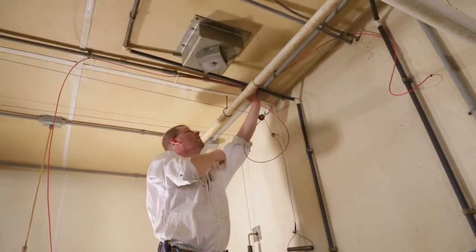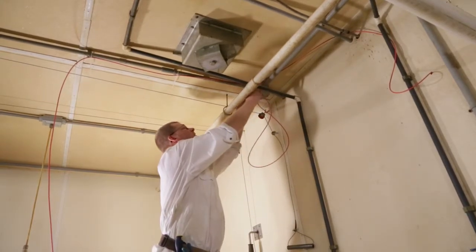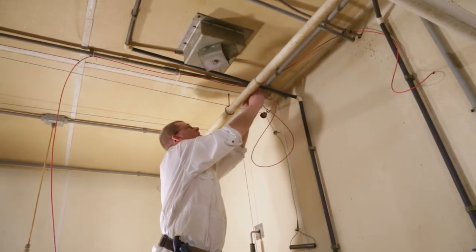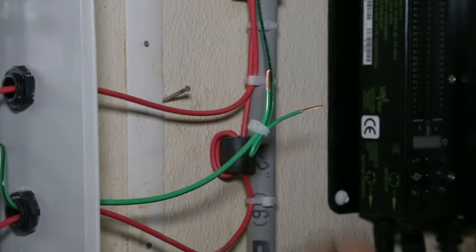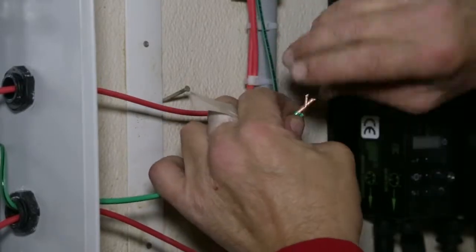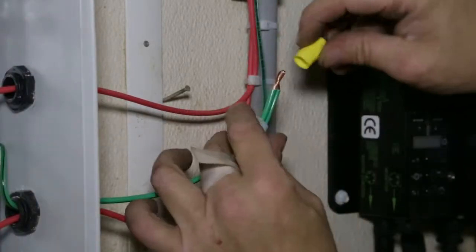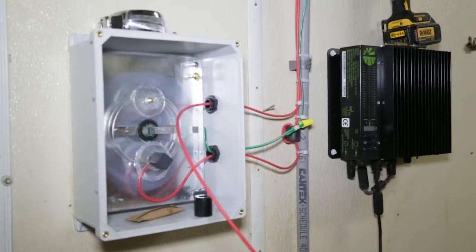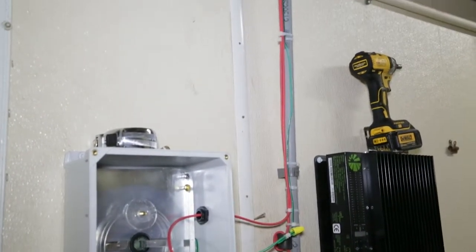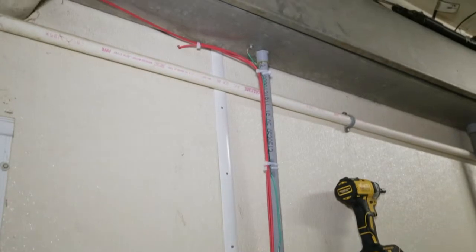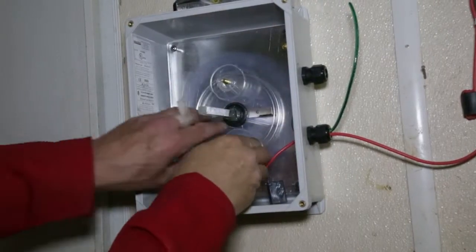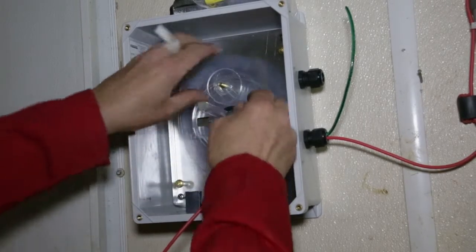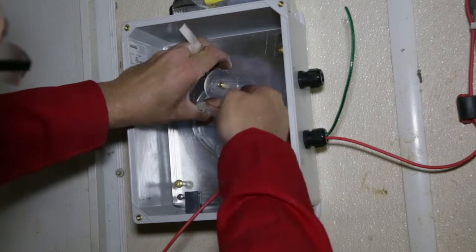Run the high voltage wire from the cold pole of the high voltage switch into the room to the nearest corona pipe run. Refer to steps 34 and 35 in the EPI Air 2 installation manual as needed. Ground the high voltage switch using the green wire coming out of the switch. Attach the ground wire to the metal wall or the main electrical ground in the room, barn or farm. The ground must have an earth ground or direct ground contact with the power supply energizing the room or switch. All gaps between plastic washers, plastic nuts and square rods must be filled completely with dielectric grease. Failure to seal the gaps will result in leaking energy inside the switch.